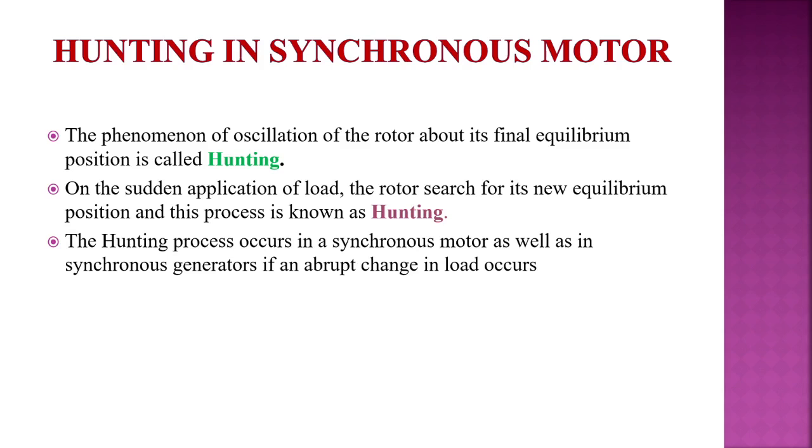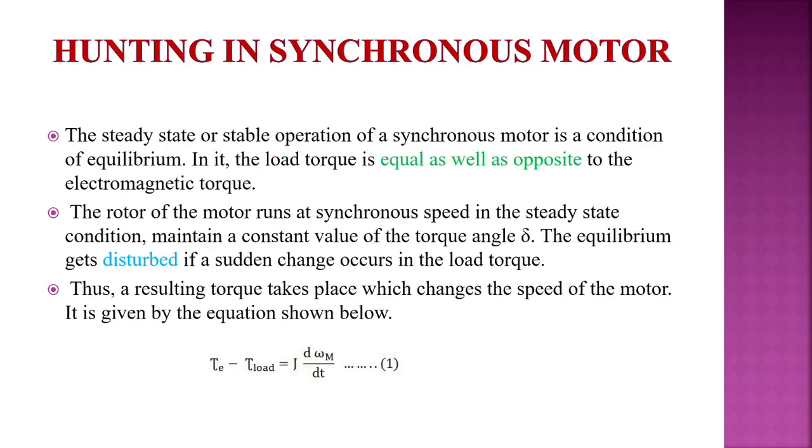The phenomenon of oscillation of the rotor about its final equilibrium position is called hunting. On sudden application of load, the rotor will search for its new equilibrium position, which is called hunting. So hunting occurs in a synchronous motor as well as in a synchronous generator if an abrupt change in load occurs. The steady state or stable operation of a synchronous motor is a condition of equilibrium. In it, the load torque is equal and opposite to the electromagnetic torque. So the rotor of the motor will run at synchronous speed in the steady state condition and will maintain a constant value of torque angle delta.